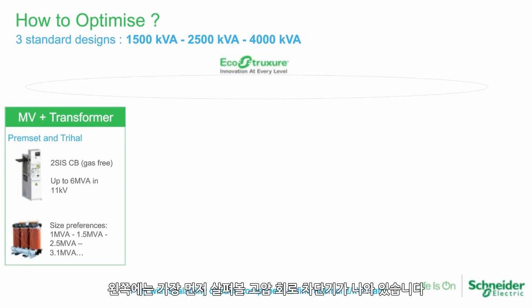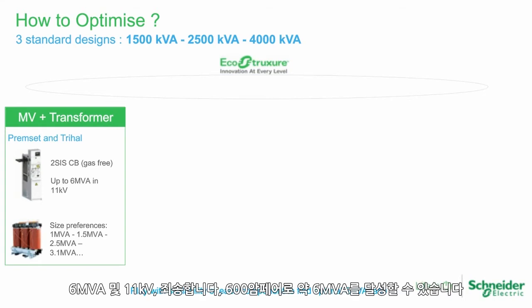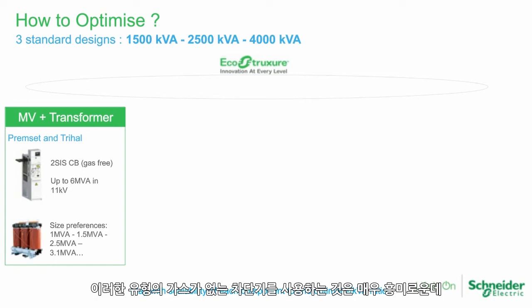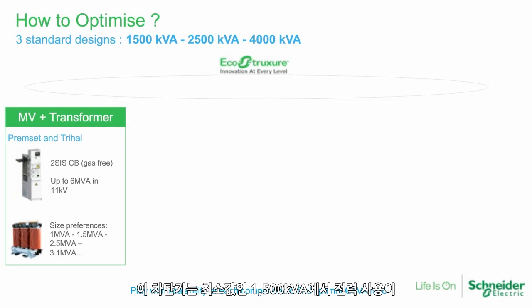And on the left side, you can see that the first thing we are considering is the medium voltage breaker. So with 11 kV, sorry, with 600 amps, we can reach about 6 MVA. So using this type of gas-free breaker is very interesting due to the fact that, as a minimum, for 1500 we will have about 30% of power capacity use for this breaker.